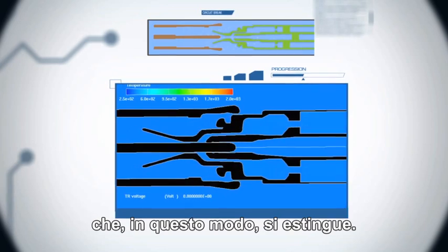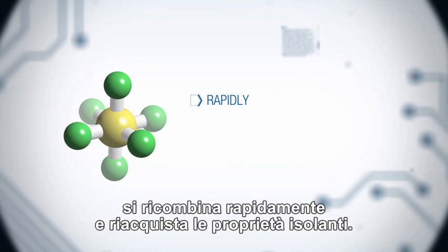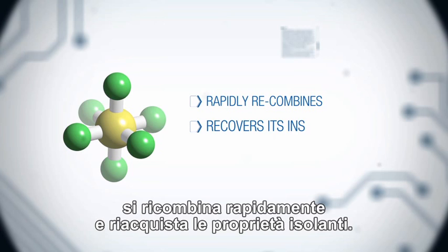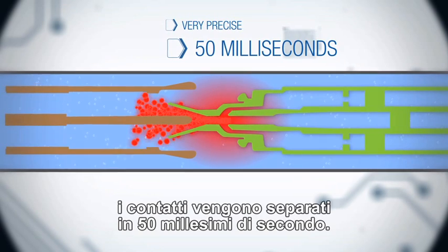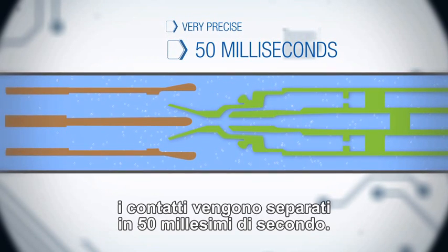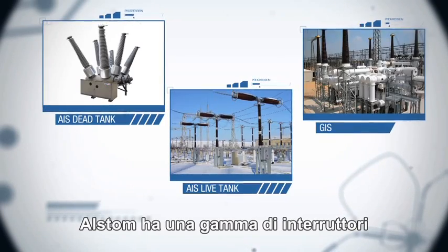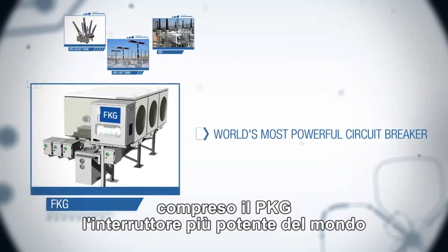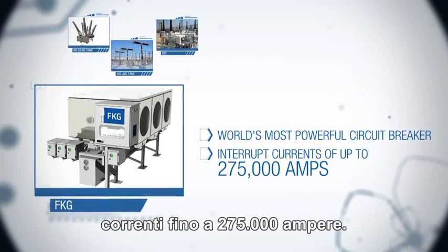The electrical arc is extinguished. This gas is replaced by cooler gas in the central zone. The SF6, thus cooled, rapidly recombines and recovers its insulating capacities. Everything is calculated very precisely — in 50 milliseconds, the contacts are separated. The circuit break has been sure and fast. Alstom offers a range of circuit breakers adapted to all electrical transmission needs, including the world's most powerful circuit breaker, Alstom's FKG, which can safely and rapidly interrupt currents of up to 275,000 amps.